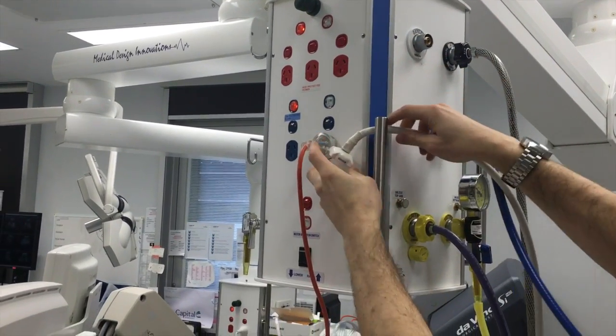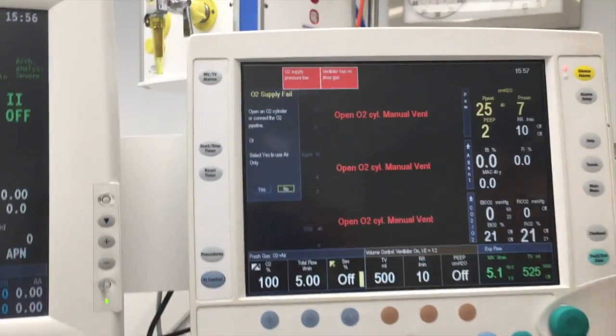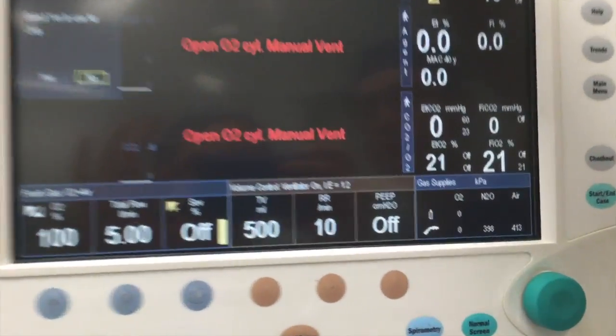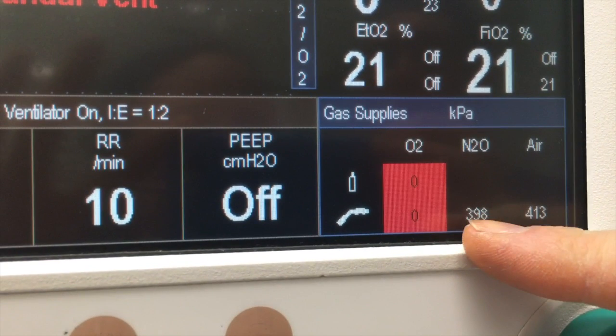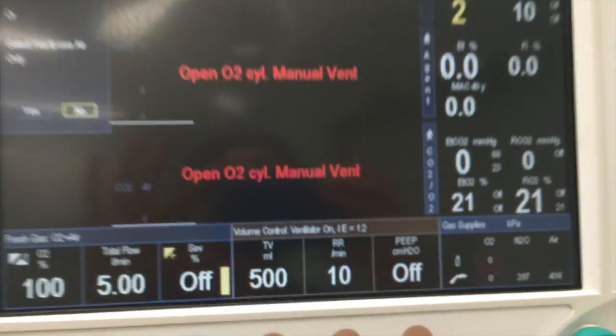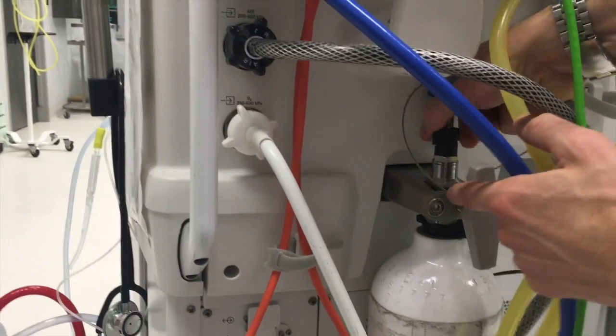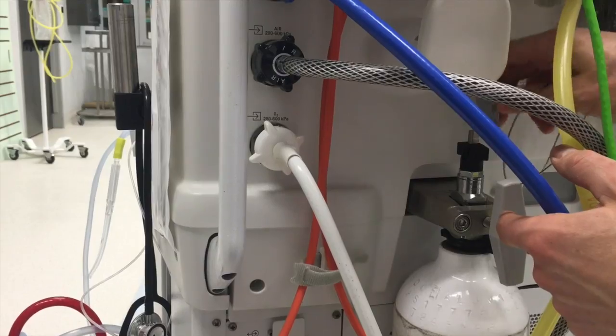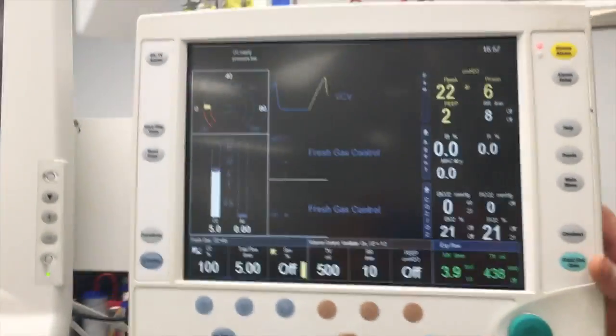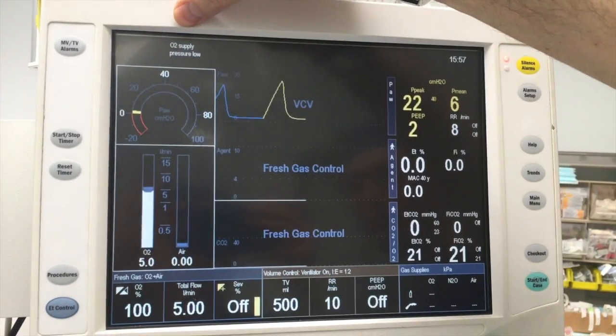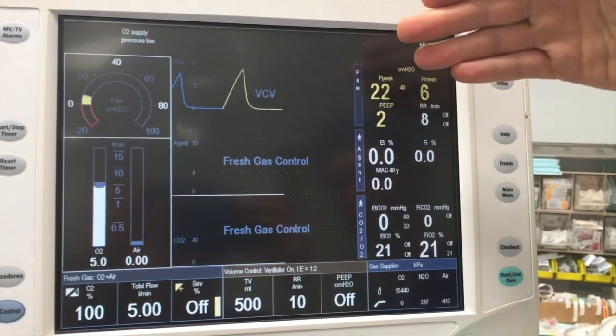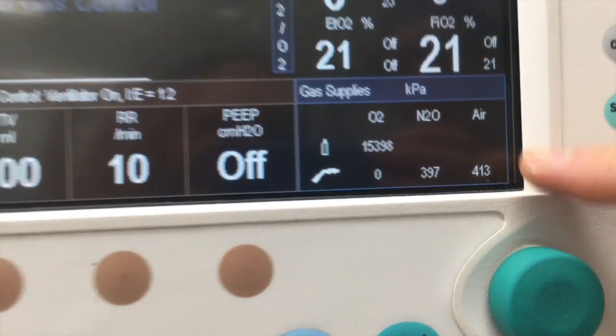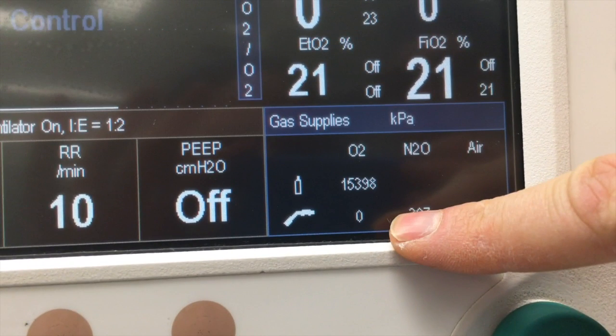Once disconnected, check that the machine has both an audible and visual alarm. Here you can see the machine has detected that both wall and cylinder oxygen supplies are 0. Check that the cylinder at the back of the machine can be turned on to supply backup oxygen to the machine itself. You can now accurately check the oxygen content of the backup cylinder by checking this pressure displayed on the gauge below. Cylinder pressure should be around 10 to 15,000 kilopascals.